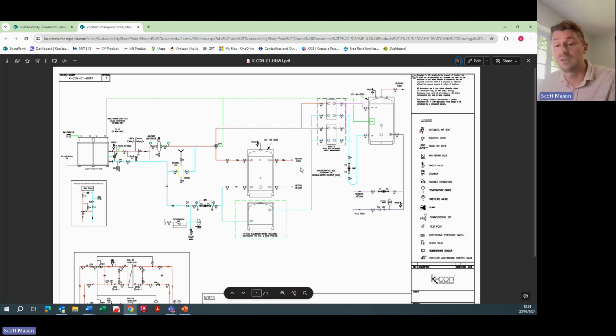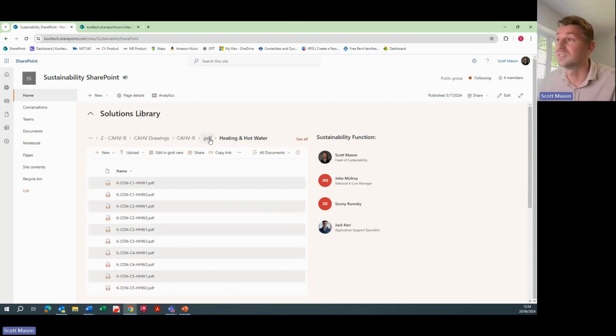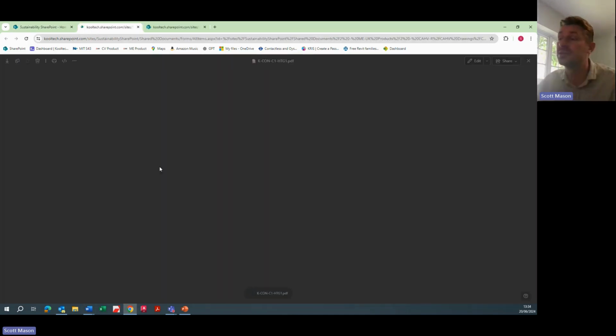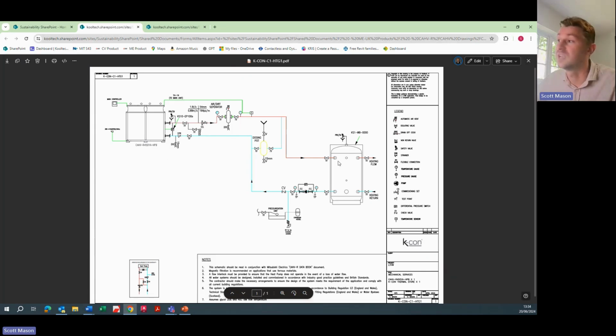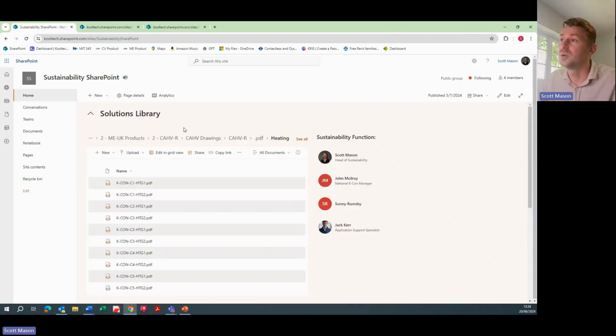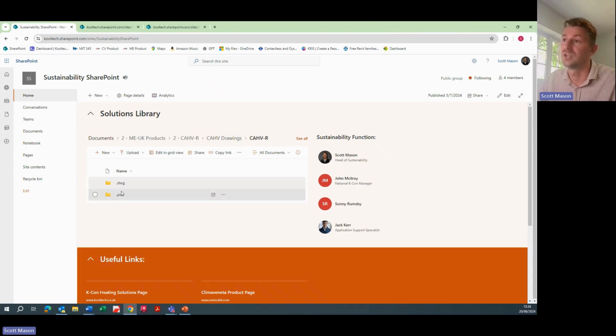So, site-specific considerations. If you wanted to break out the system and just have a system for each, you would do something like this. A heating arrangement is going to be way more simplified. We've got the CAHV-R serving a thermal storage vessel and returning. You can see we're flowing into the thermal store. The thermal store will have 2-inch tap-ins on it because that's our line size, so we don't end up with a load of noise and turbulence in the vessel. That then goes off to our heating circuit, does what it needs to do, and the return will be at a slightly lower temperature.